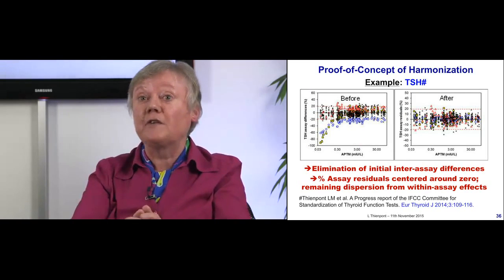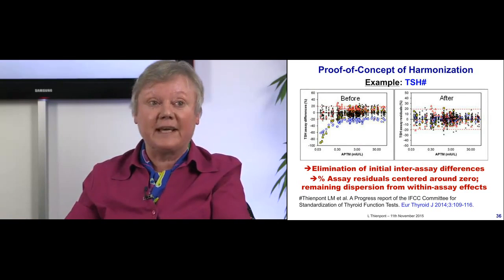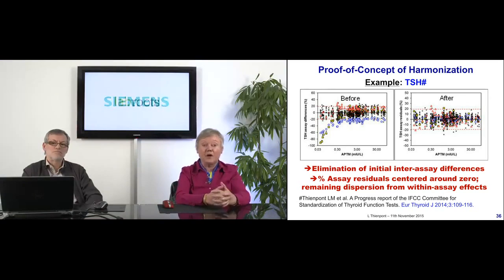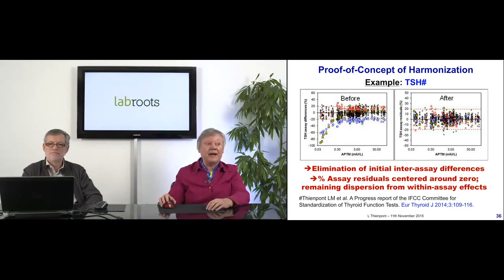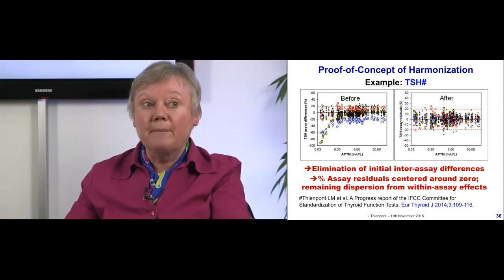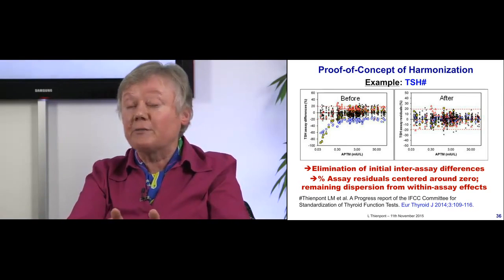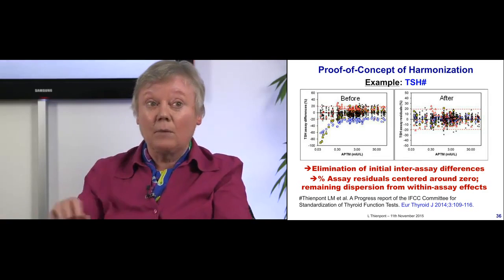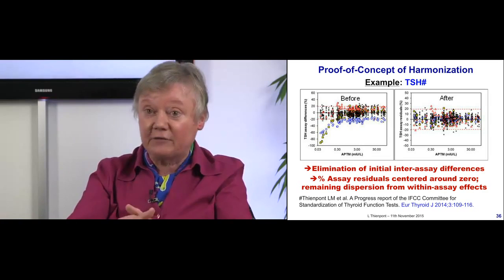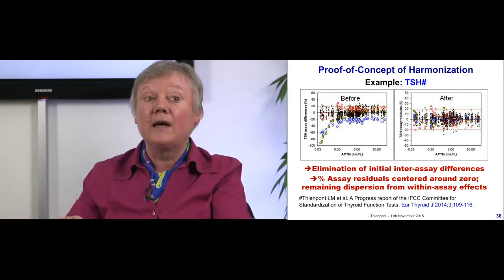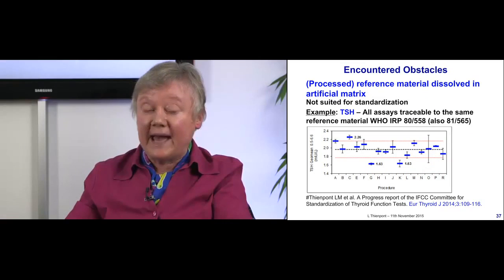I show the proof of concept of harmonization for TSH. We performed a method comparison with 16 immunoassays, presenting the percentage difference of results for a panel of samples. The most discrepant assays are shown in different colors — blue symbols and red triangles. Before the harmonization process there are clear differences between immunoassays; after the harmonization process the inter-assay differences are eliminated, percentage assay residuals are nicely centered around zero, and the remaining dispersion is from within-assay effects.